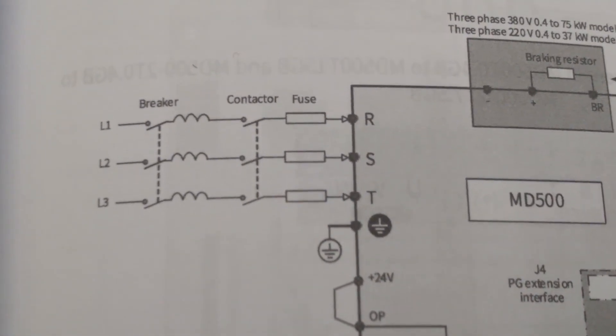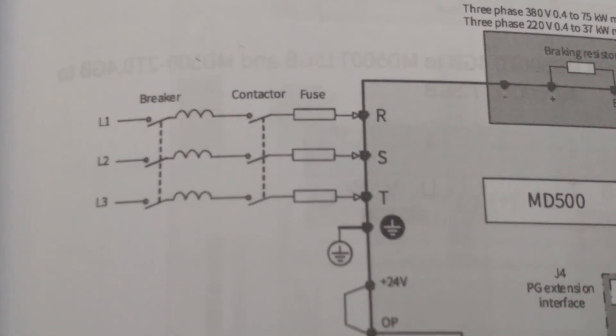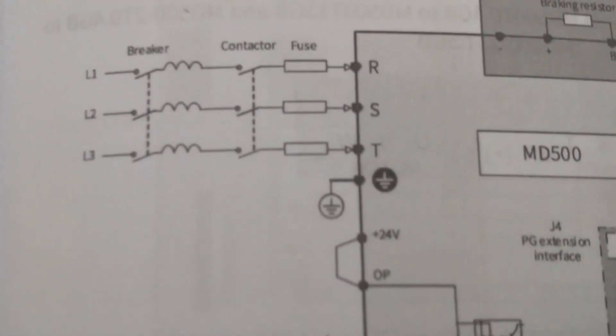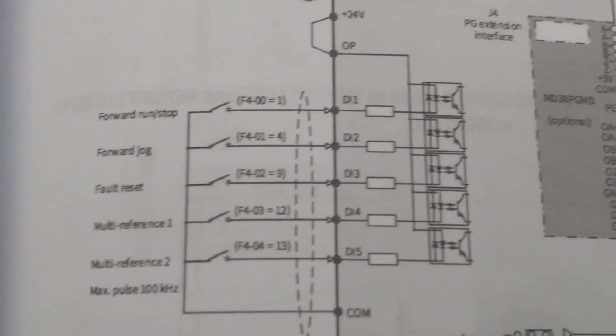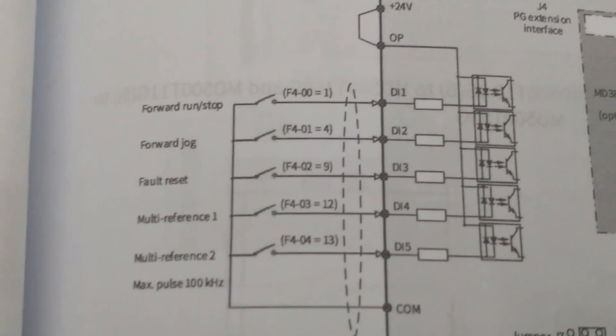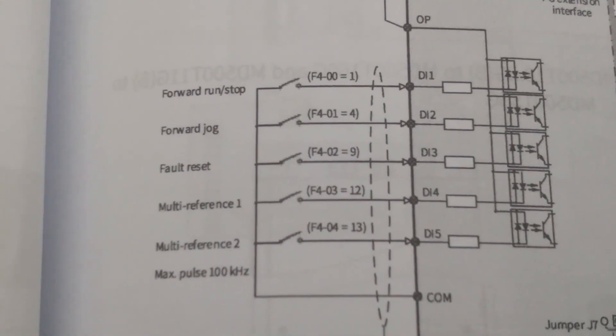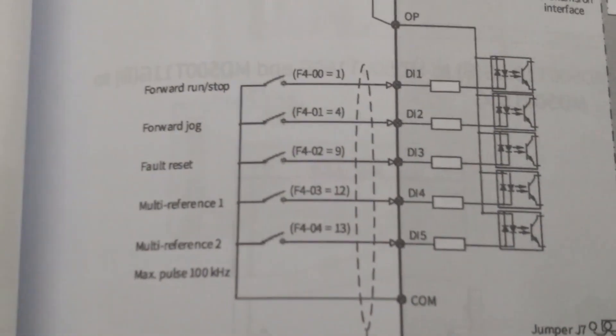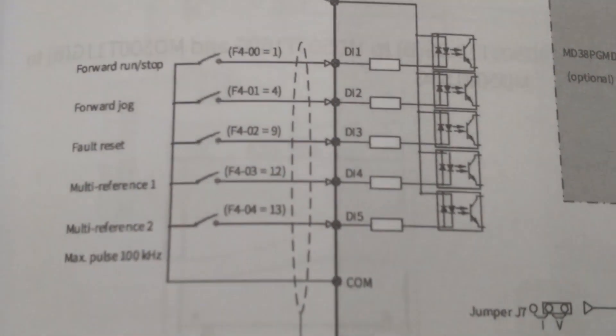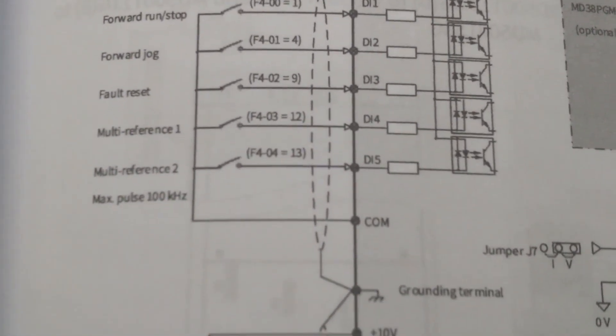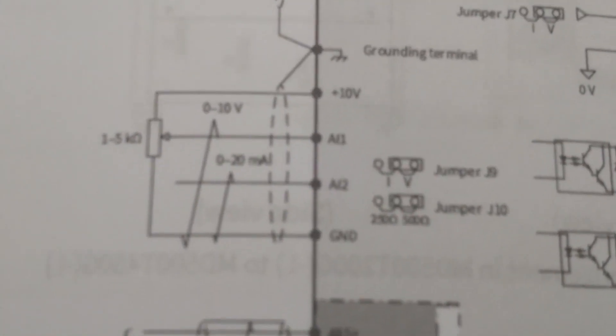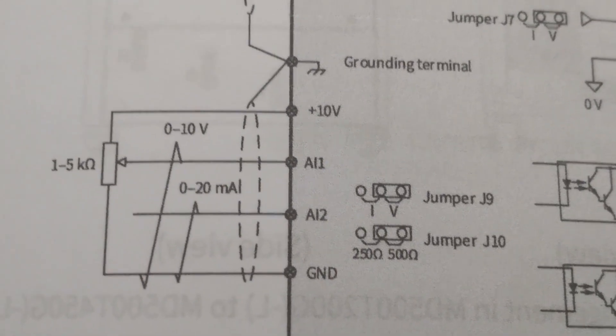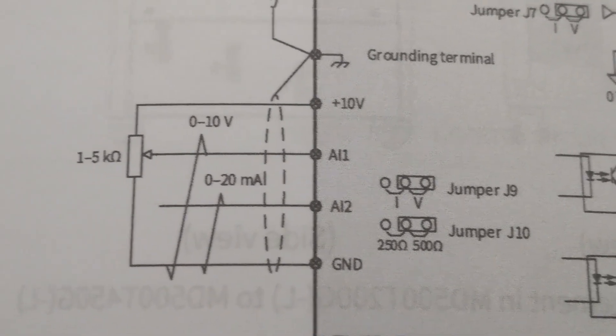Main supply should be connected to VFD using suitable rating of breaker, reactor, contactor, and fuses. VFD input terminals are wired by taking wire from common terminal and connected to push buttons, selector switches, and then to VFD input. External potentiometer is connected to VFD using +10 volt, AI1, and GND terminal.